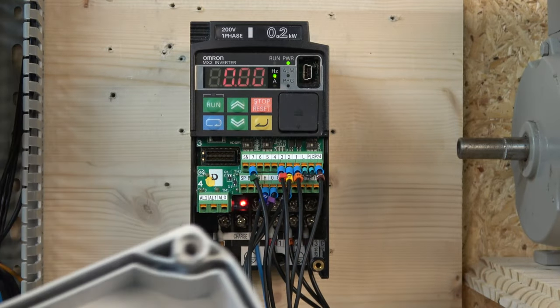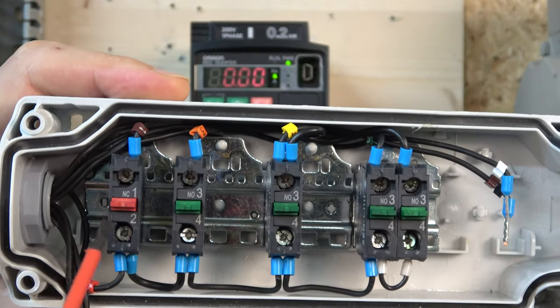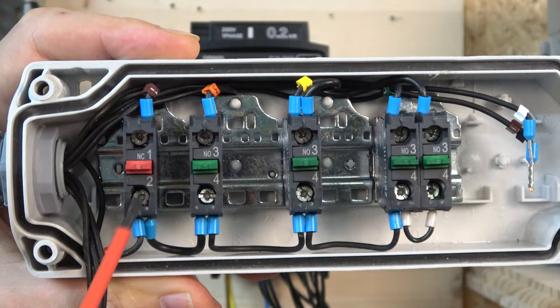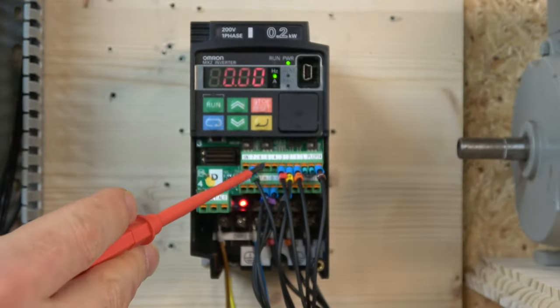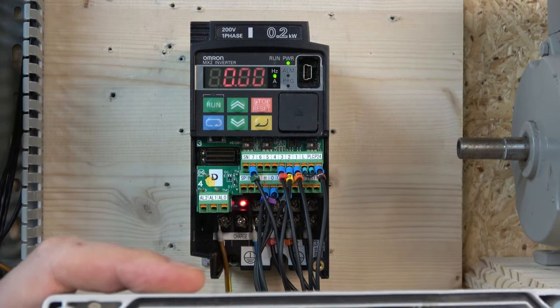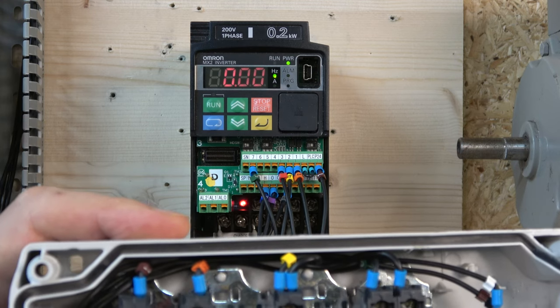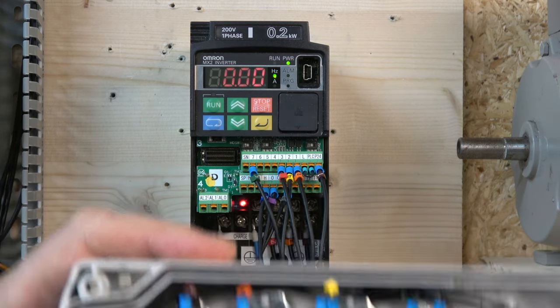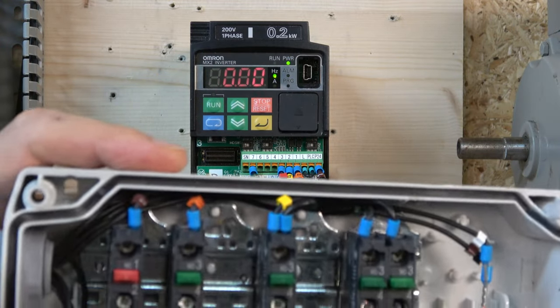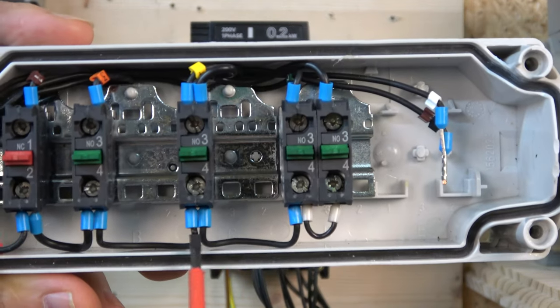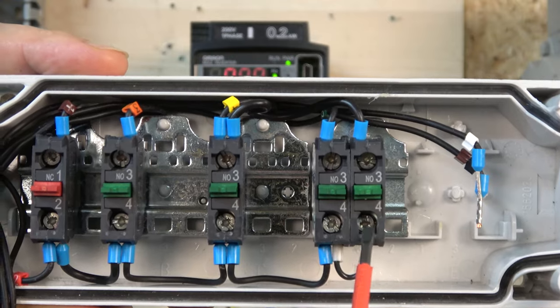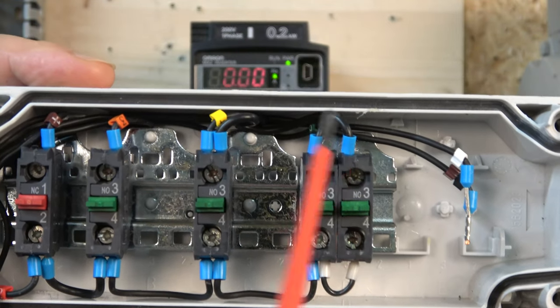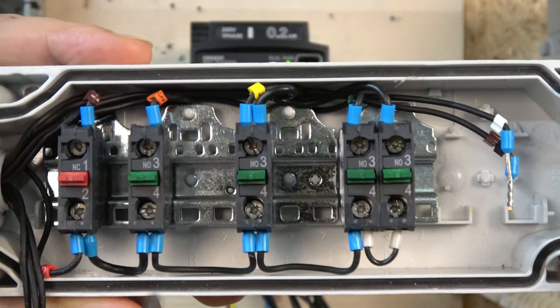So for the wiring we have terminal P24 coming to our normally closed contact which is our e-stop, and as you can see I have number 2 in down there and that number 2 is going back to terminal 3, which by default is normally open contact for external trip. But because my contact is closed, it's not tripping. I'll show you how to reverse those contacts. From there on you can send the power to all the switches.